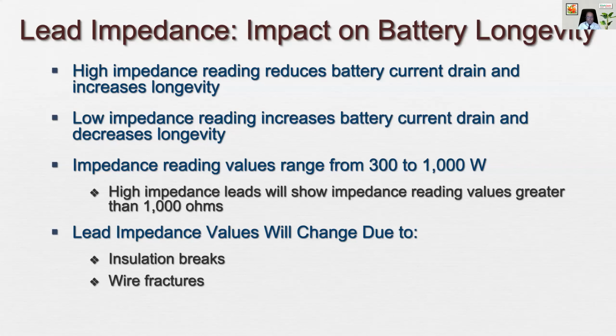Normally, if you take an electrical wire, even a 15-meter wire of copper or any good conductor, it will have an impedance of less than 5 ohms. So it is built into the leads. There is a tendency from the manufacturers to produce higher impedance leads, which don't allow too much electric current wastage. So usually now we are seeing an electrical impedance of 800 to 1000 ohms from the newly manufactured leads.